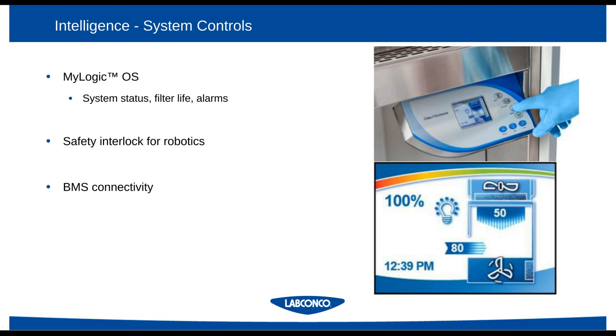As Simon was discussing, it's also very important to consider the impact that the enclosure will have on an automated liquid handler that has panels. And so when those panels come off, the safety interlock method that was provided by those panels is removed. And to correct for that and to still maintain that safety factor, it's important that the enclosure provides an ability to have a safety interlock.